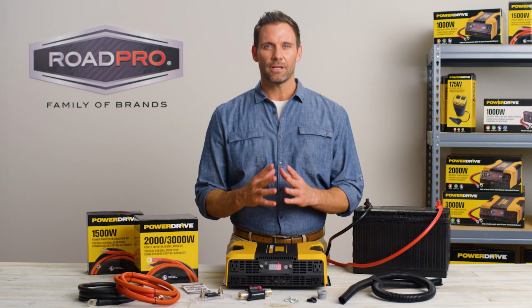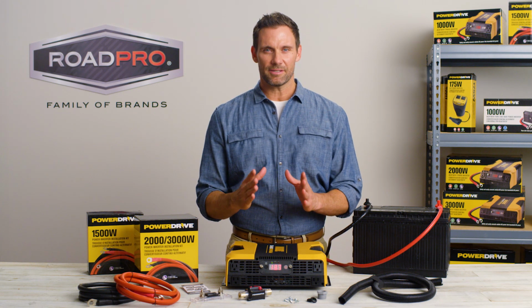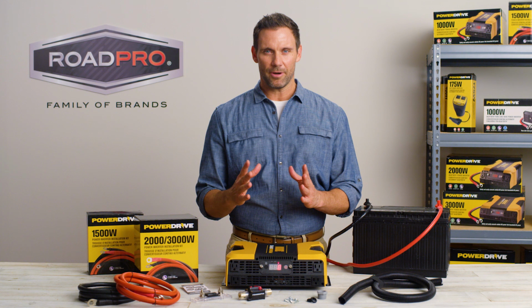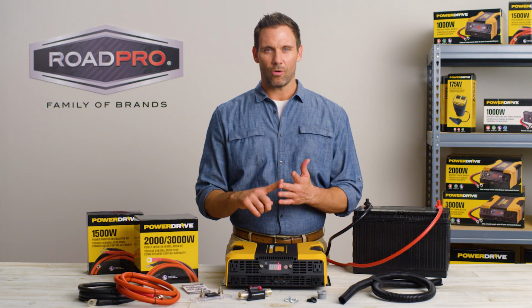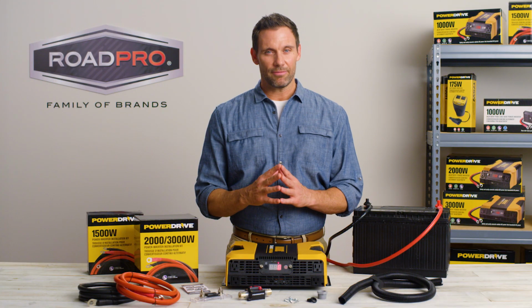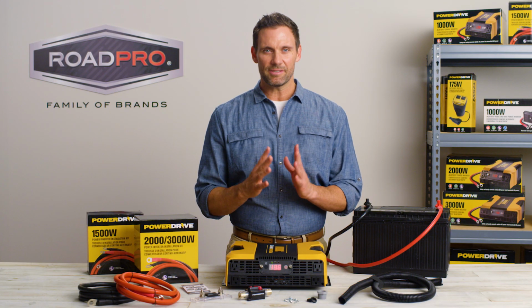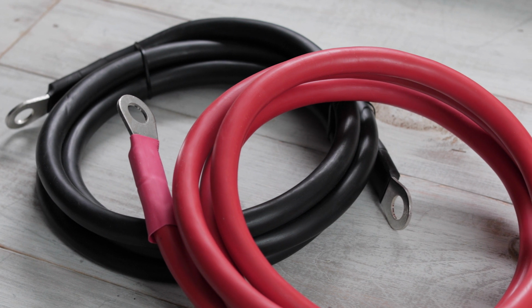To install your inverter, you will need the proper length and size cables, fuse or circuit breaker, mounting screws, grommets, and sheathing. Powerdrive inverters come equipped with a set of properly sized cables; however, they may not be long enough to reach the installation location. Measure the length from the battery to where you will install the inverter to determine the cable length.